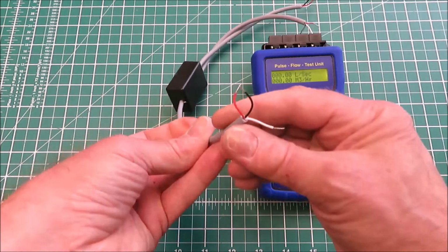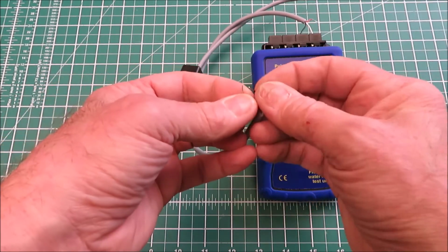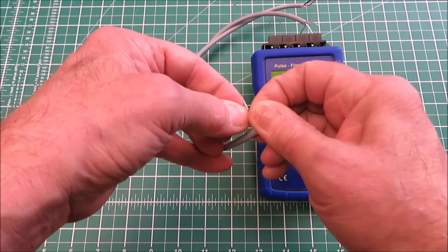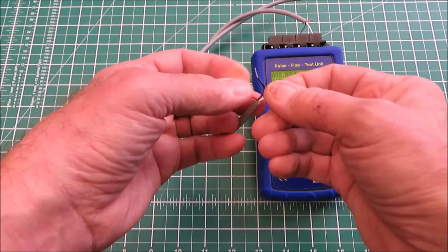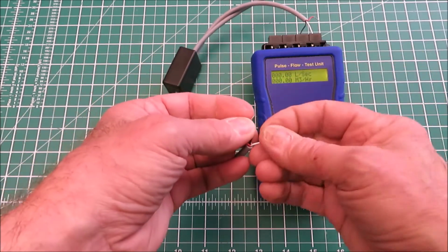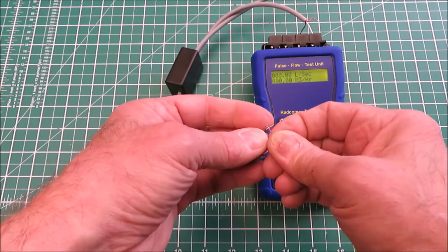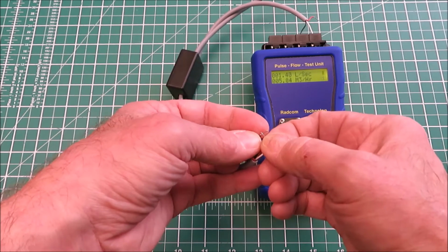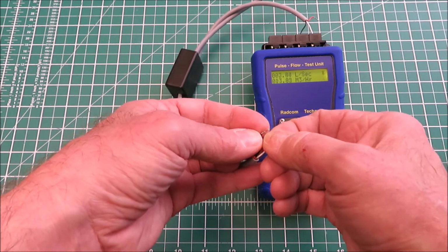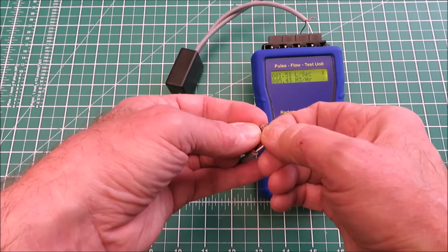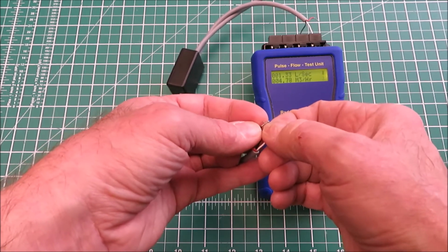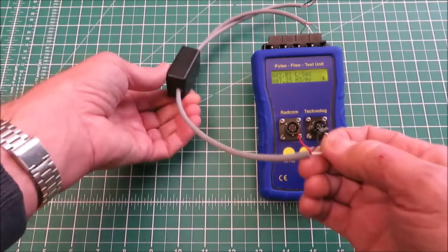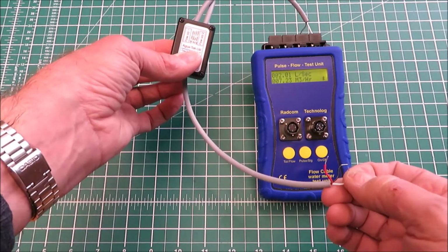And then coming back, obviously this time if I touch the black and red, we shouldn't see a flow, which we don't. But if I touch the black and white, we should start to see the flow. So that's mimicking a pulse output from a flow sensor going into the splitter that is splitting the flow off.